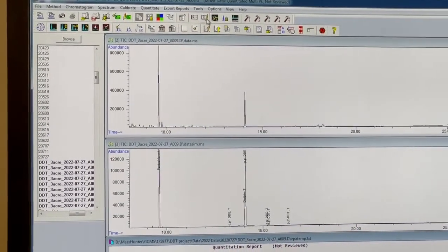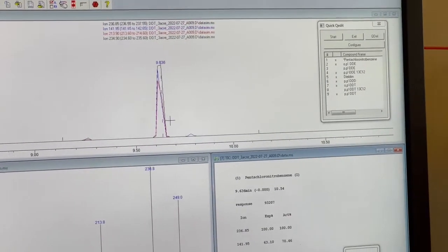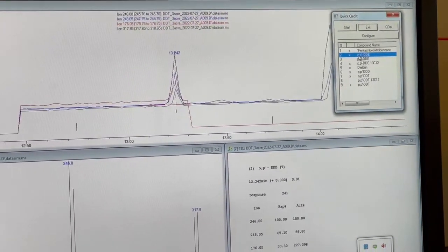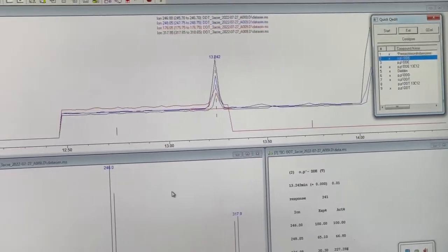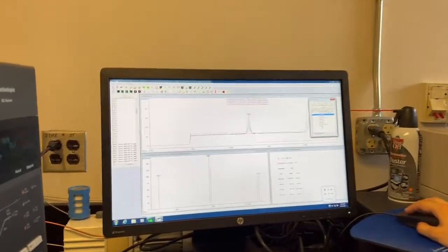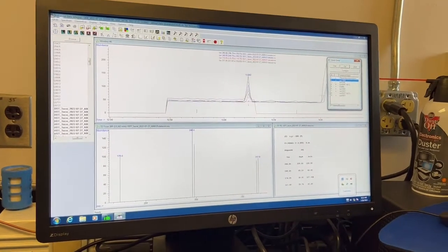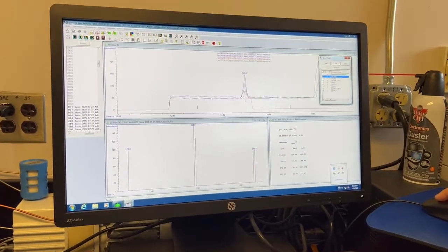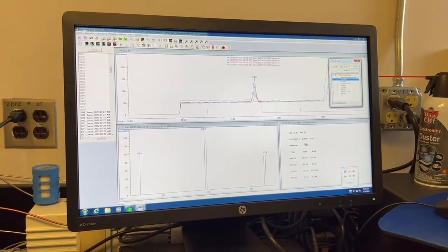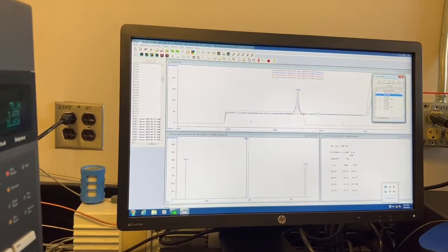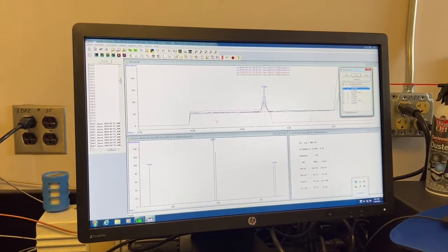So how we analyze the sample is kind of the same as the calibration, except we don't calibrate it. So we go to Quantitate, Calculate, and then go back to QEdit. We can see our internal standards there. That's good. But because this is our sand blank, we don't want to see any peaks for the rest of the samples. We might see something teeny tiny, but our response is 241, whereas it was in the hundreds of thousands earlier. So it's still going to quantitate as zero.